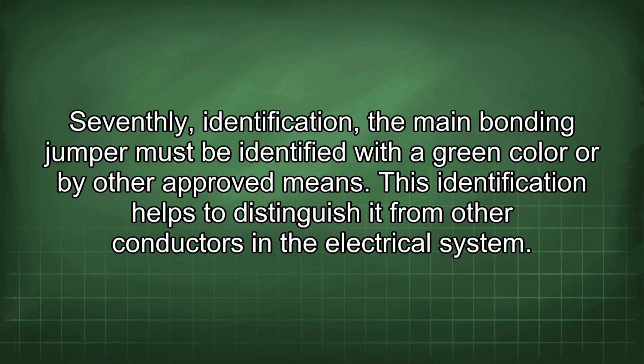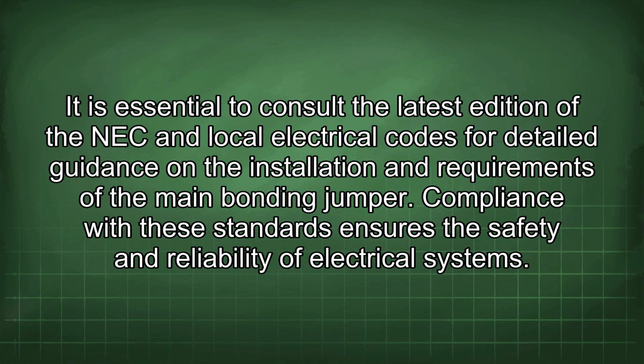Seventhly, identification. The main bonding jumper must be identified with a green color or by other approved means. This identification helps to distinguish it from other conductors in the electrical system. It is essential to consult the latest edition of the NEC and local electrical codes for detailed guidance on the installation and requirements of the main bonding jumper. Compliance with these standards ensures the safety and reliability of electrical systems.